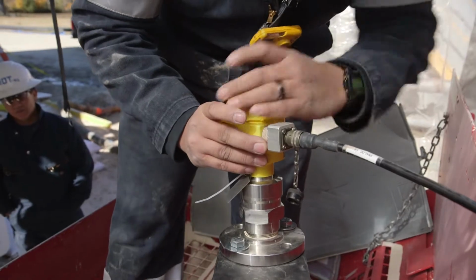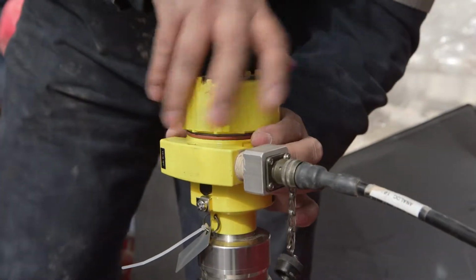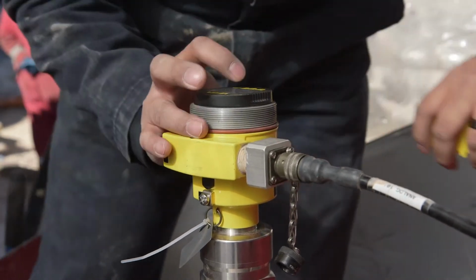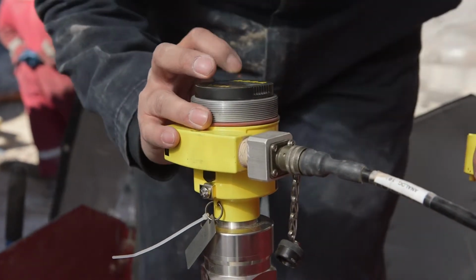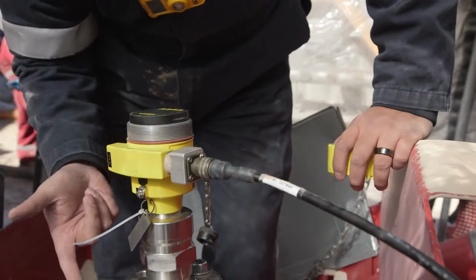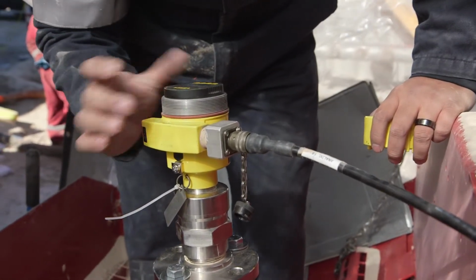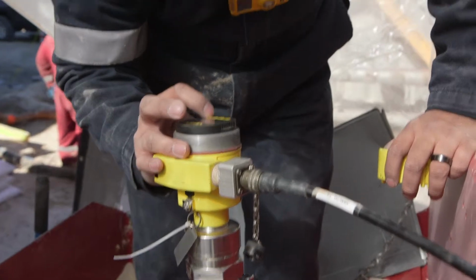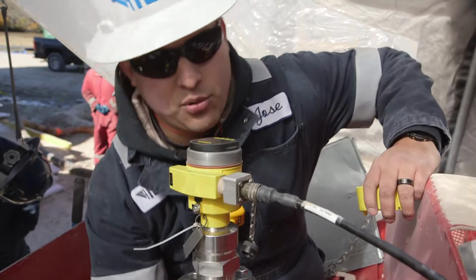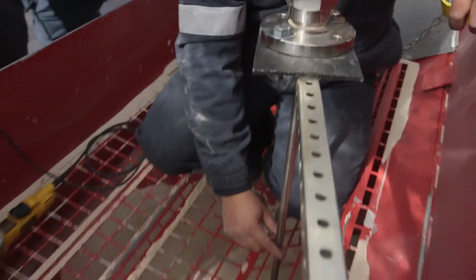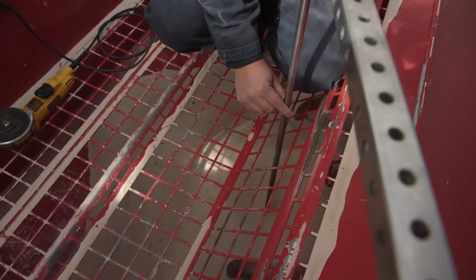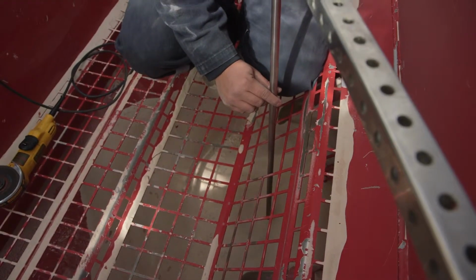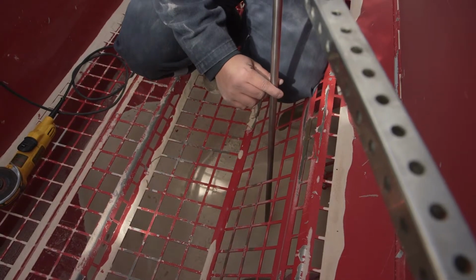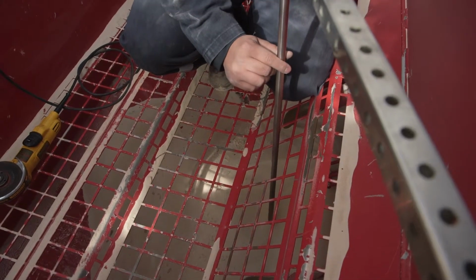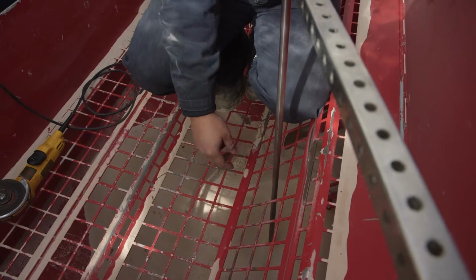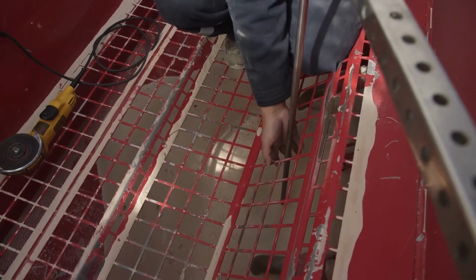Calibrate the probe. Right now we're reading the signal from the grate. Right now what I'm doing is the false signal suppression, to suppress the signal that's coming off the grate. We'll explain this more in actual training. And to test it, just grab the probe a little bit. Make sure it's changing as you move your hand up and down. And if possible, grab it underneath the grate. Make sure you're getting a reading down there.